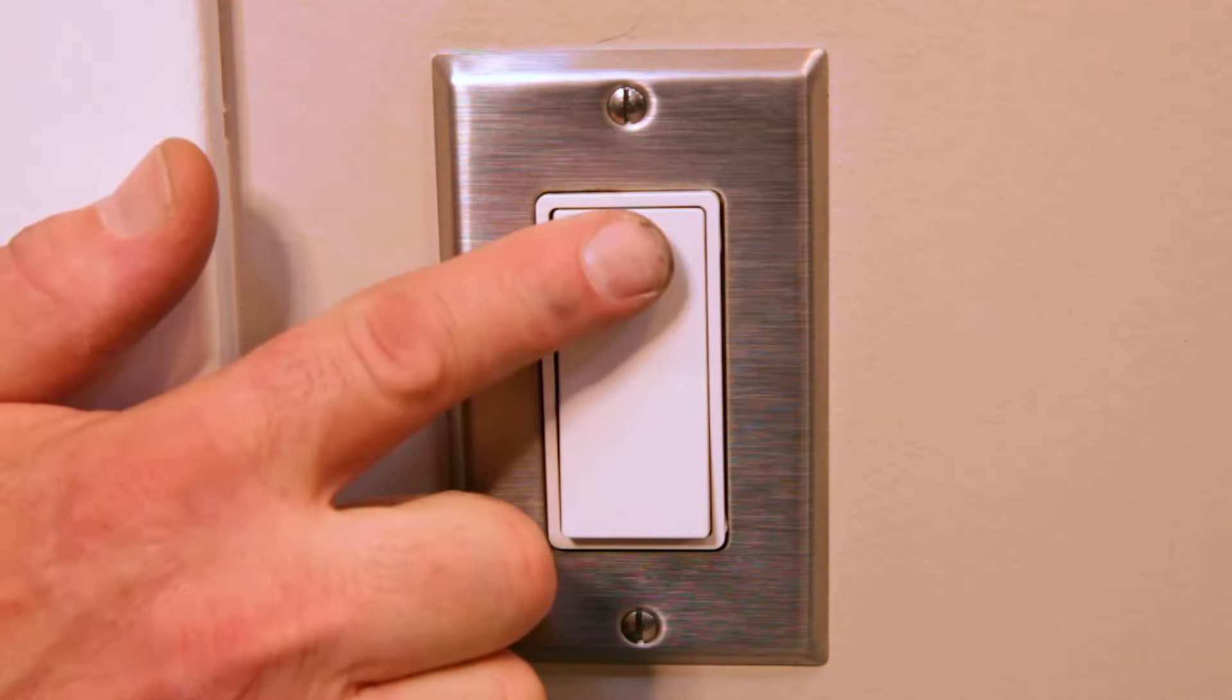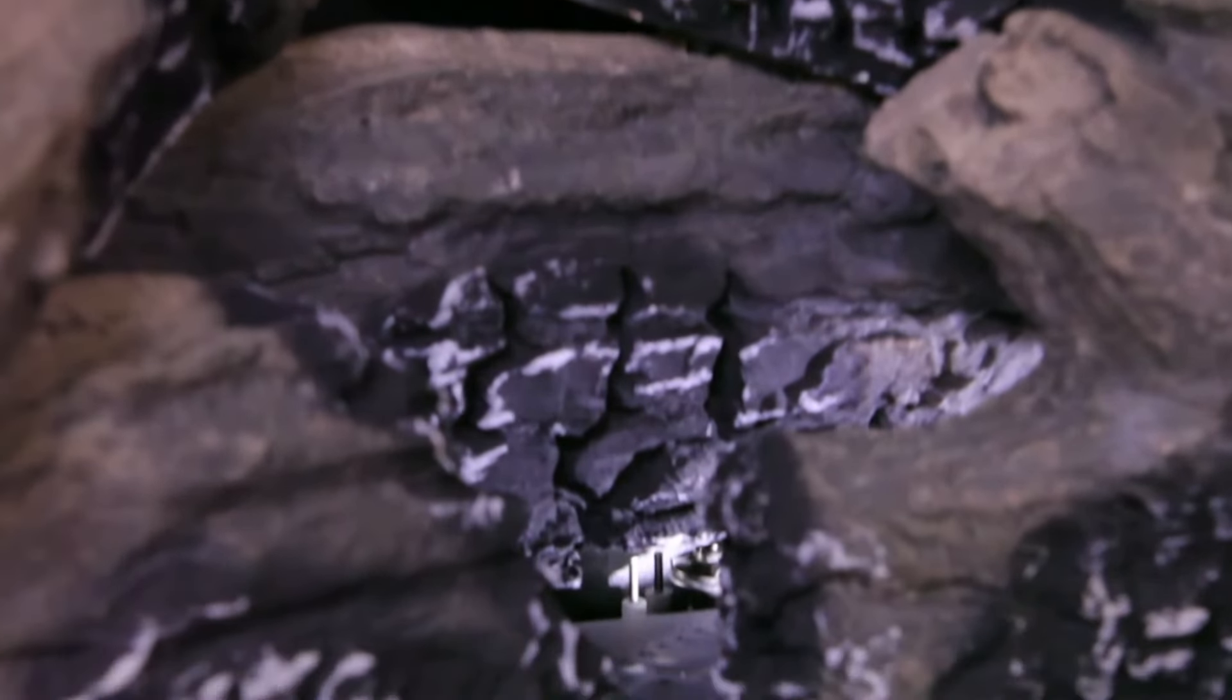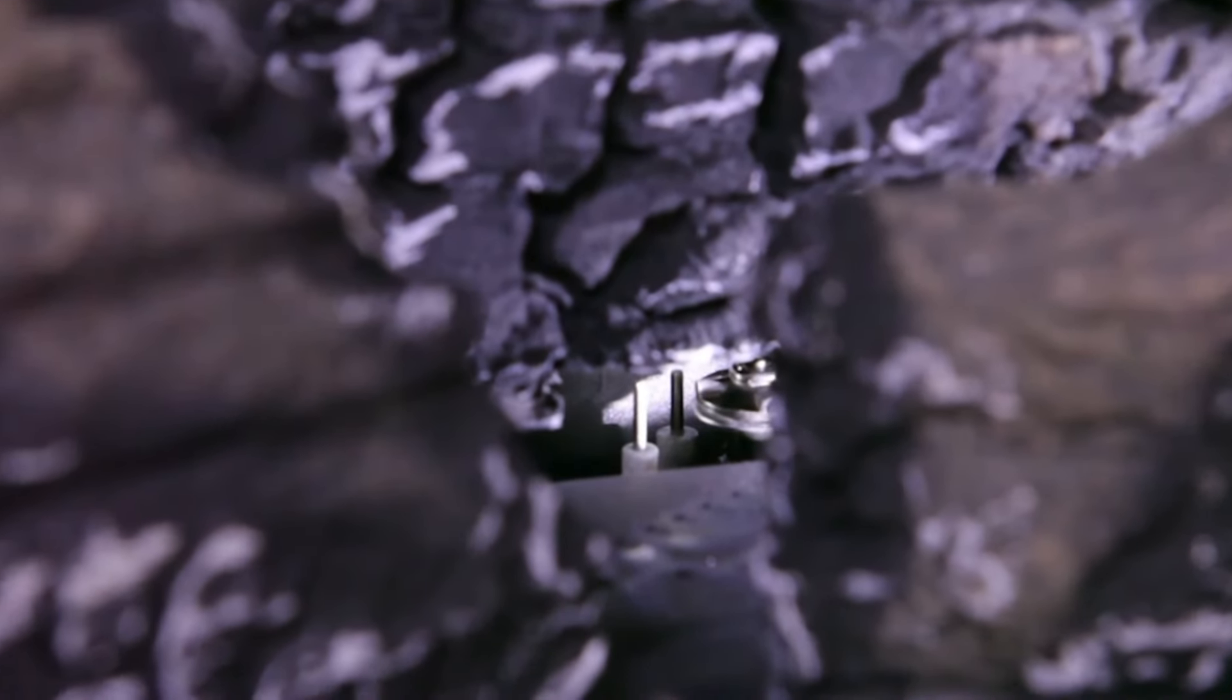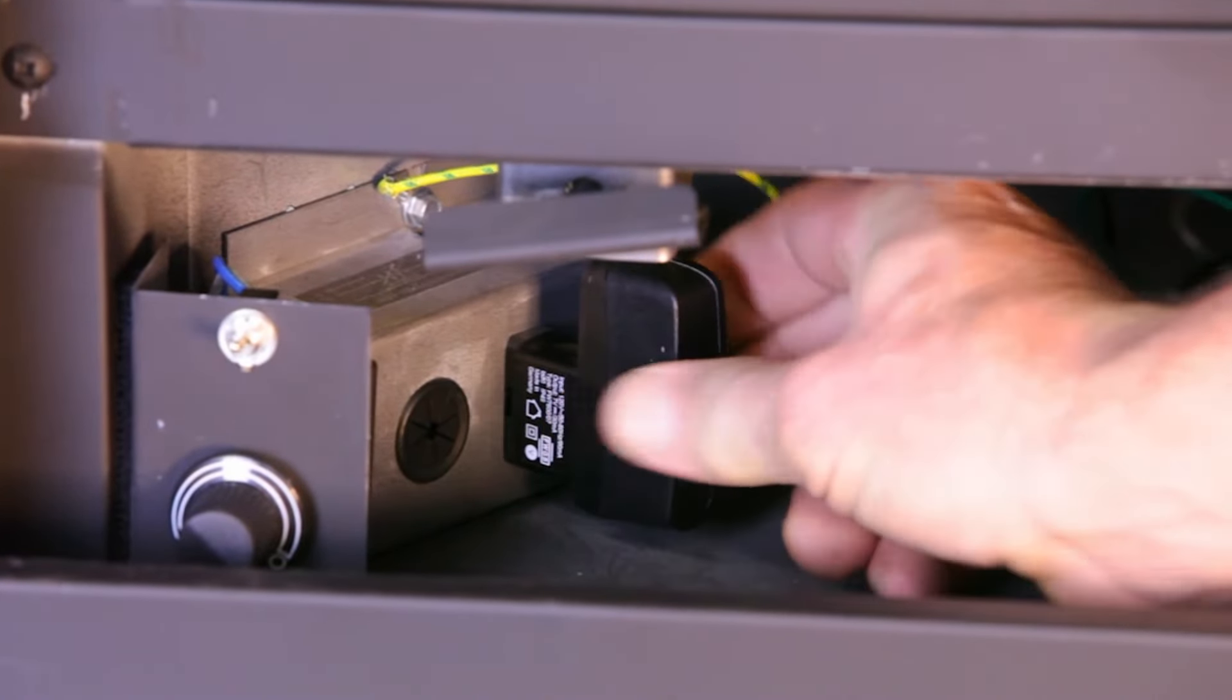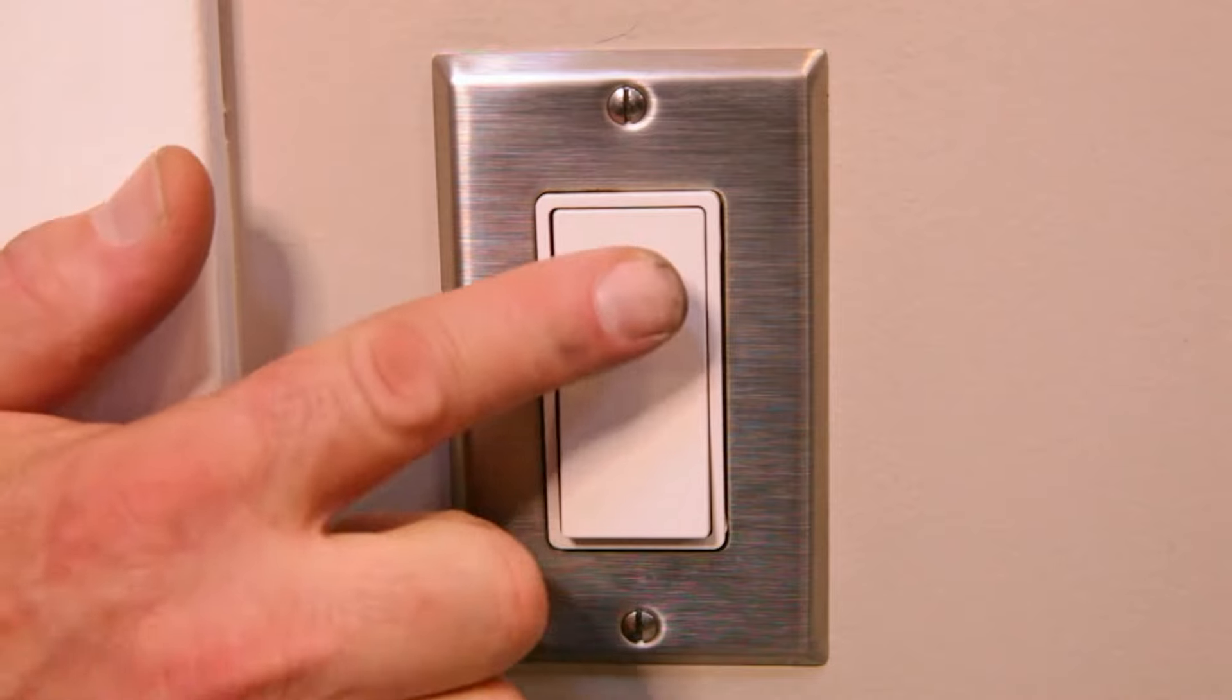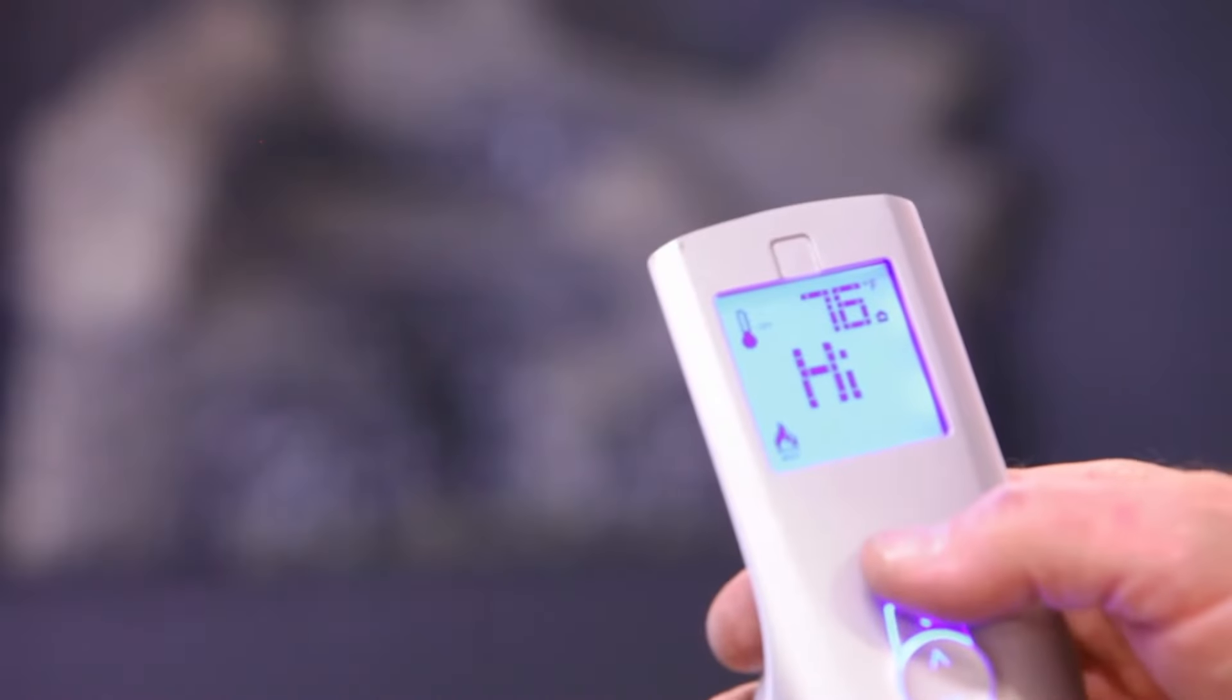When you first turn on your fireplace, initiate call for heat by turning on a wall switch or using your optional remote control. If you don't see a spark at the pilot hood, then check to see if there is electricity to the fireplace. Plug in the transformer, it may be concealed, and try the switch or remote again.